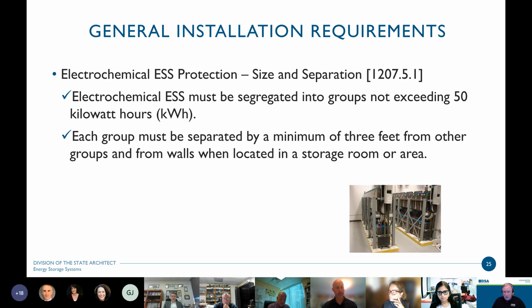So electrochemical protection, we're talking size and separation. This is one of the elements that changed going into the 2022 code, in that battery arrays have to be segregated into groups that do not exceed 50 kilowatt hours, and each group must be separated by a minimum of 3 feet from other groups and from walls when located in any kind of a storage room or area. So it's those separation requirements and size requirements that really come into play now for 2022. For those campuses that may have installed systems under prior code editions, this will certainly be an impact that you'll recognize.